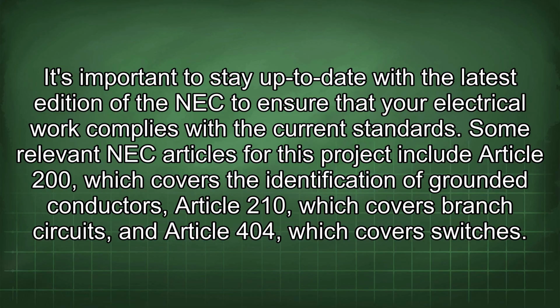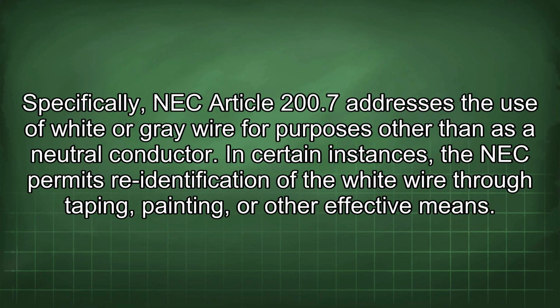Some relevant NEC articles for this project include Article 200, which covers the identification of grounded conductors, Article 210, which covers branch circuits, and Article 404, which covers switches. Specifically, NEC Article 200.7 addresses the use of white or grey wire for purposes other than as a neutral conductor. In certain instances, the NEC permits re-identification of the white wire through taping, painting, or other effective means.